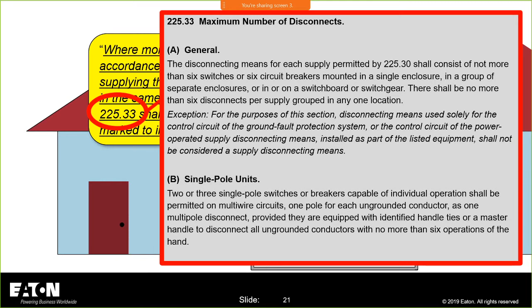Now, the reference they make to 225.33, again, that's the maximum number of disconnects requirement. So that's, again, your 6 switches, 6 disconnect rule. And that's all I have to say about that one. Discard those changes and come back.